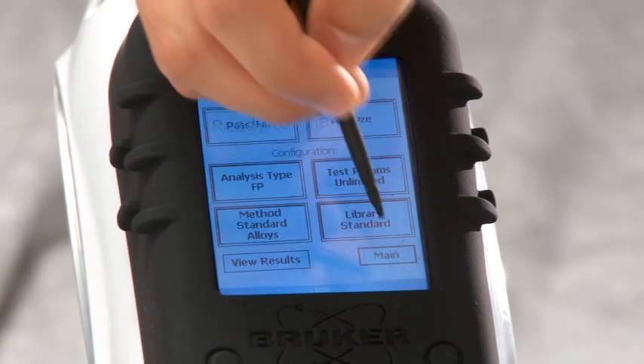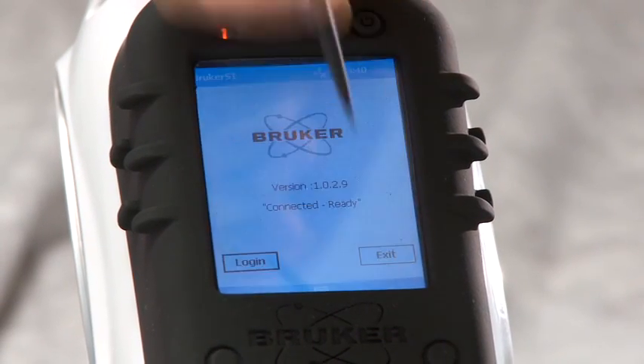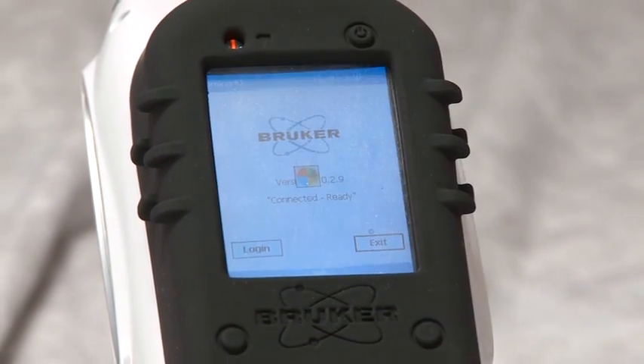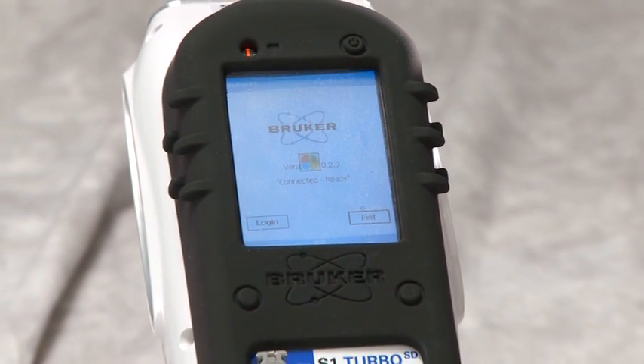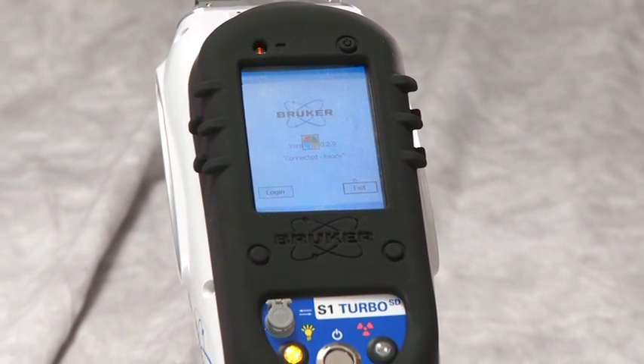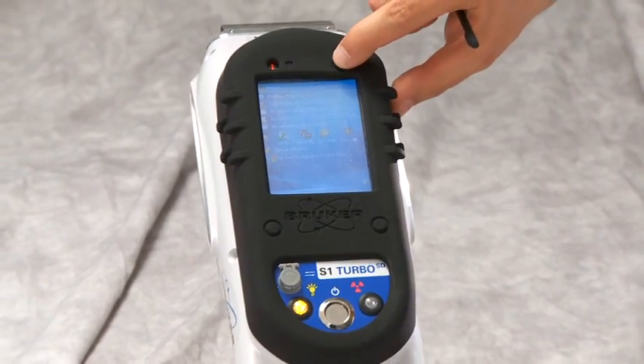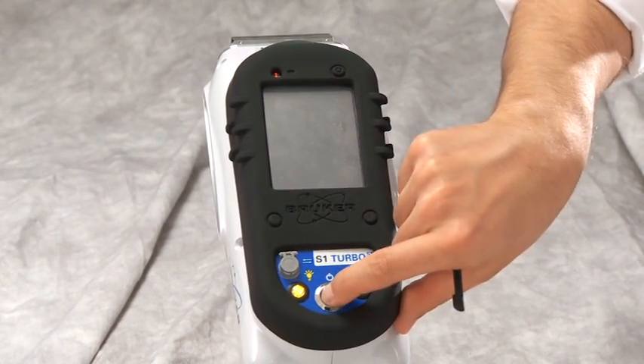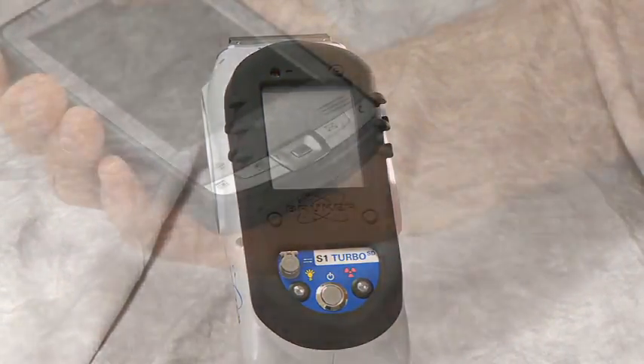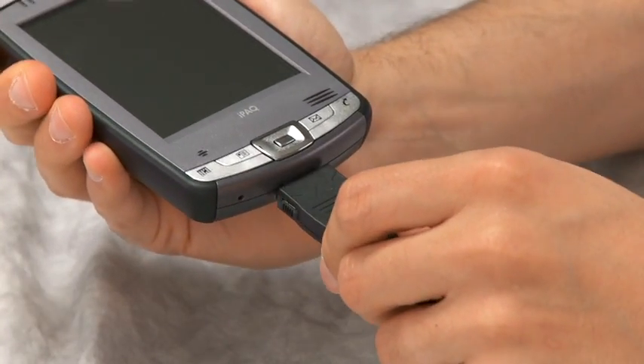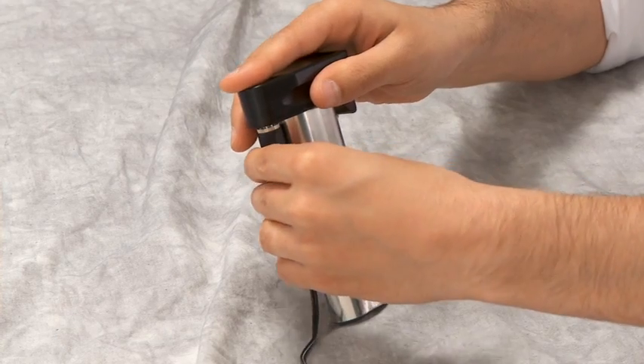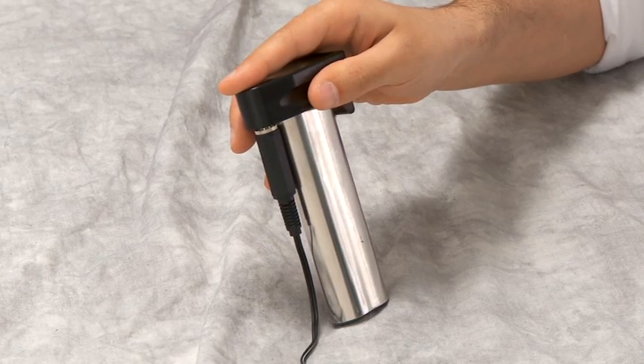To shut down the instrument when you have completed your work, simply tap the right-hand button on the bottom of each screen. Eventually, you will reach the PDA home screen. When at the PDA home screen, press the PDA power button and the analyzer's power button to turn each off. It is recommended that while the S1 Turbo is not in use, the PDA and the analyzer battery should be attached to their chargers.